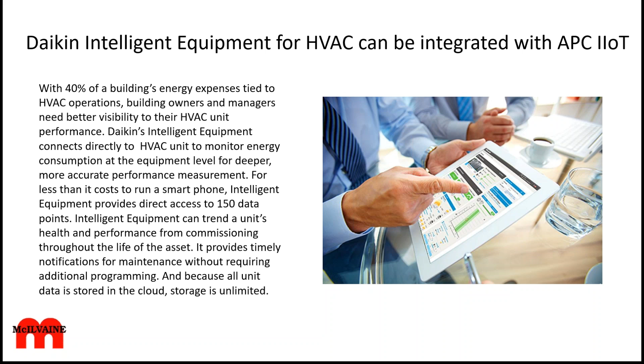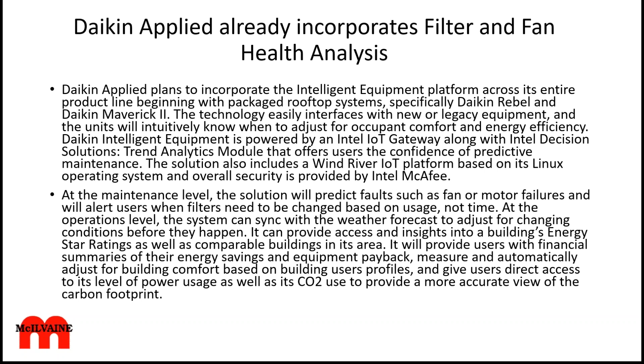So the overlap with air pollution control is that things like filters and fans are already monitored in their intelligent equipment platform. Specifically, the Daikin Rebel and Daikin Maverick 2 technologies interface with newer and legacy equipment, and they measure the performance of the fans and the pressure drop across the HVAC filters. Doing the same thing for dust collectors should be possible, and as we'll see, dust collectors are often and typically in the same plants with the industrial ventilation HVAC.